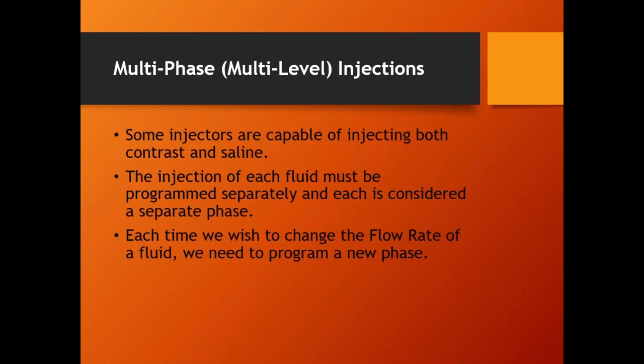All right. Is there anything that we should be aware of on that screen when it's completed? Oh, yeah, this particular one, they don't all do this, but this particular one will pop up a screen. It'll give you the total flow rate or the total volume injected for each fluid, the maximum pressure achieved in the syringes during the injection, whether you hit your pressure limit or not. It'll tell you if you did not get to the maximum or the required flow rate that you asked for.